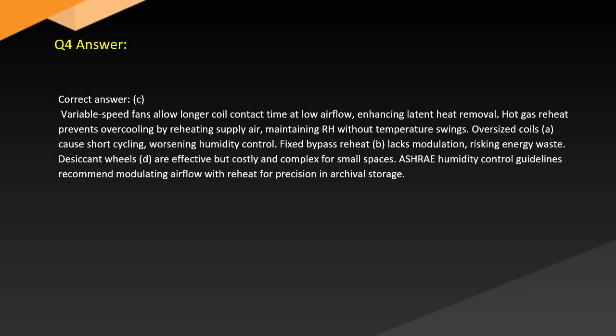Answer. Correct answer: C. Variable speed fans allow longer coil contact time at low airflow, enhancing latent heat removal. Hot gas reheat prevents overcooling by reheating supply air, maintaining RH without temperature swings. Oversized coils (A) cause short cycling, worsening humidity control. Fixed bypass reheat (B) lacks modulation, risking energy waste. Desiccant wheels (D) are effective but costly and complex for small spaces. ASHRAE humidity control guidelines recommend modulating airflow with reheat for precision in archival storage.